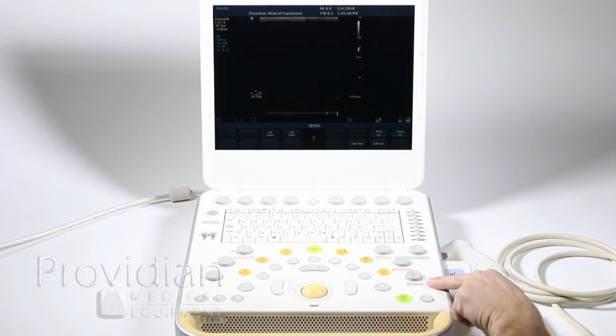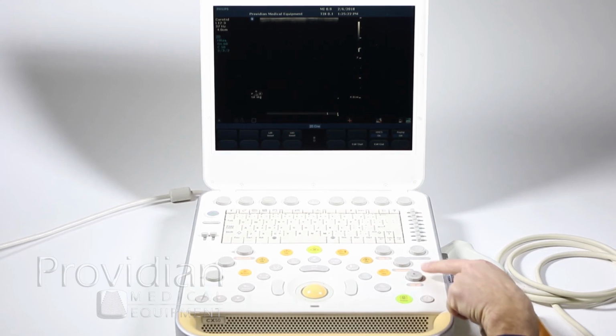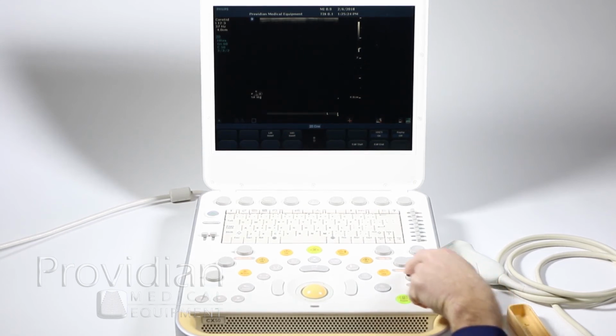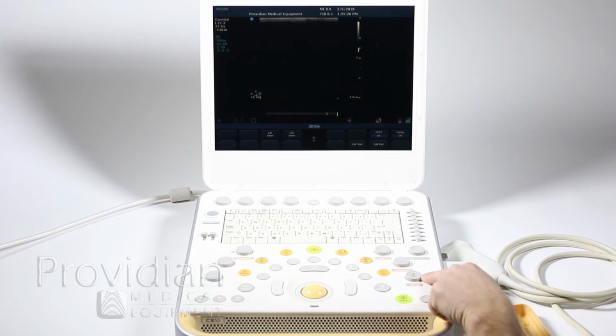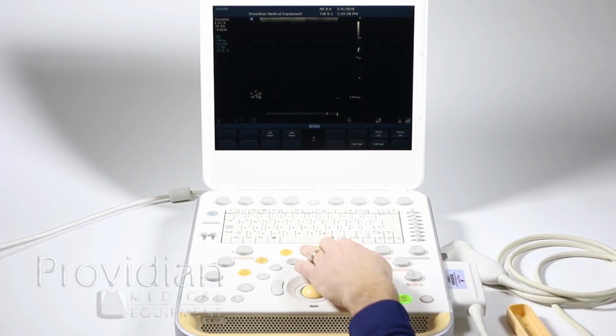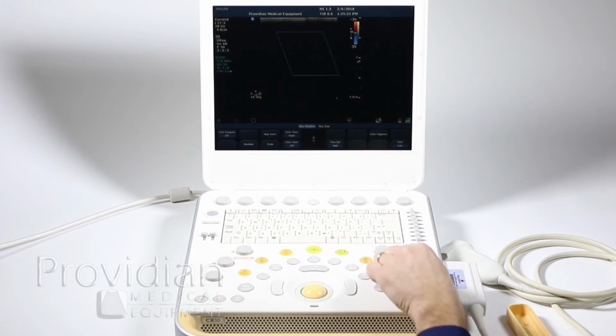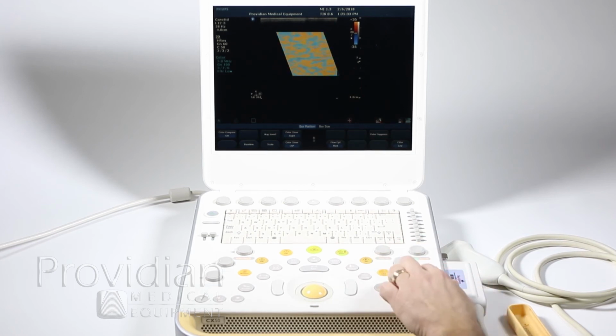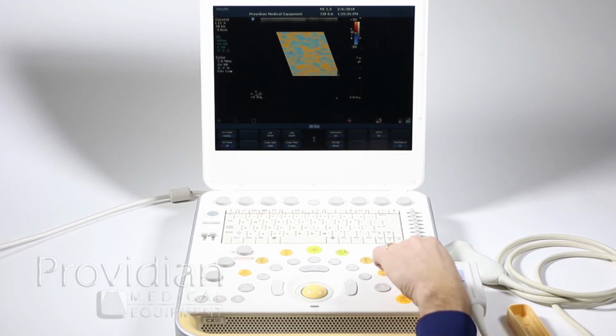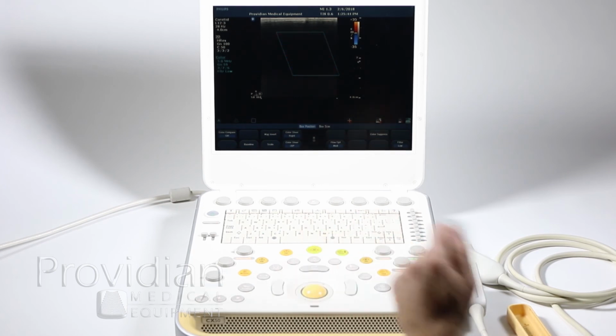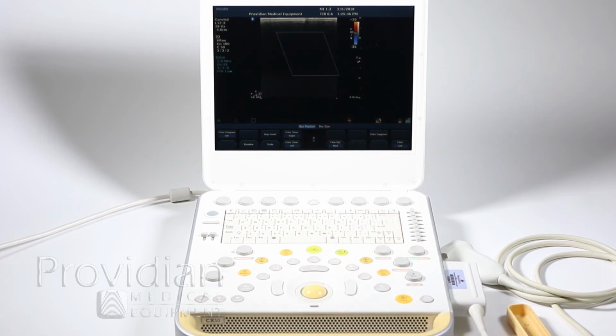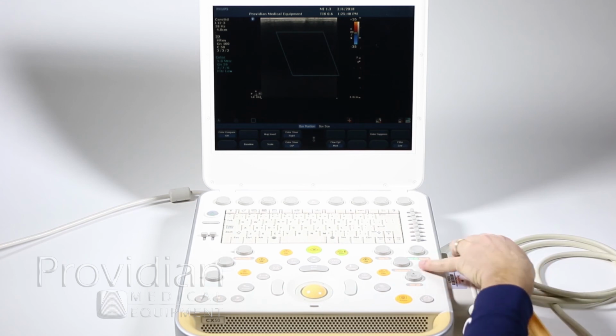Your gain, now this gain also says active mode, so if you push down, it will change the gain on whatever you choose to be the active mode. For example, if I have color on, I can twist this to change the active color, but if I push it down, I will increase the grayscale or the gain on the 2D image. Push it down again, and I can turn that gain down on the color, and the same goes for pulse wave or any of the other options available.